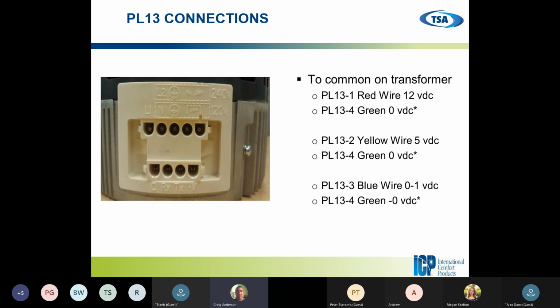So this is just like I stated, our readings that we're going to read on the motor. Red to green, 12 volts DC. Yellow to green, 5 volts DC. Blue and green, we should have a little bit of fluctuation between 0 and 1. That's if you don't have the tester to plug into the motor. We can do it with our voltmeter.